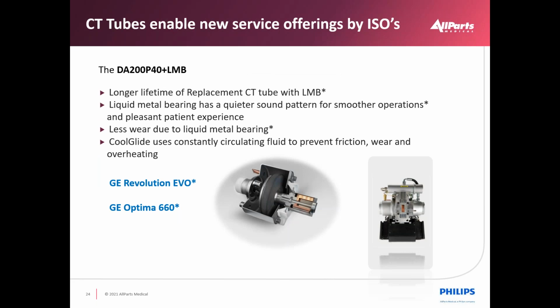So one of the advantages of using a liquid bearing tube is it should increase the life of the tube, because the ball bearings are no longer ball bearings but liquid metal, which has quieter operation and tighter tolerances for smoother operation. In this case, Dunlee calls it Cool Glide, which reduces friction, so tube life should be extended due to less bearing failure. And obviously an enabler for the GE Revolution EVO product and the Optima 660 products as well.